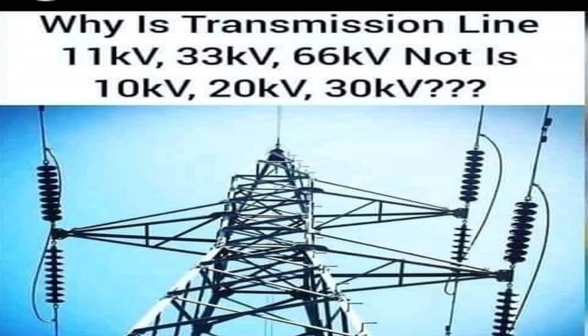Why is the transmission line voltage 11 kilovolt, 33 kilovolt, 66, and not 10, 20, 30, 40 or whatever? The choice of transmission line voltages such as 11, 33, and 66 kilovolt instead of 10, 20, and 30 involves a combination of technical, economic, and practical considerations. These voltage levels are not arbitrary; they are determined through comprehensive analysis to optimize the efficiency, cost effectiveness, and reliability of the power transmission system.